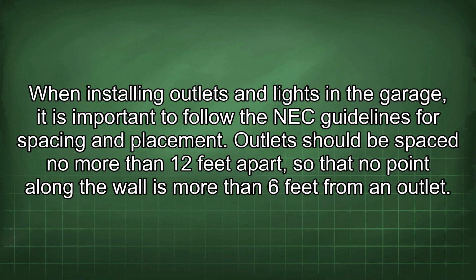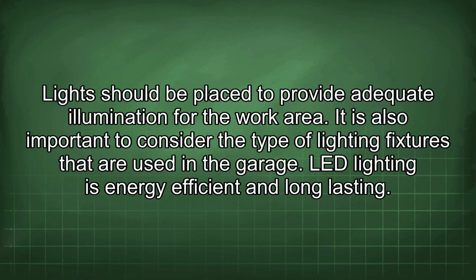When installing outlets and lights in the garage, it is important to follow the NEC guidelines for spacing and placement. Outlets should be spaced no more than 12 feet apart, so that no point along the wall is more than 6 feet from an outlet. Lights should be placed to provide adequate illumination for the work area.